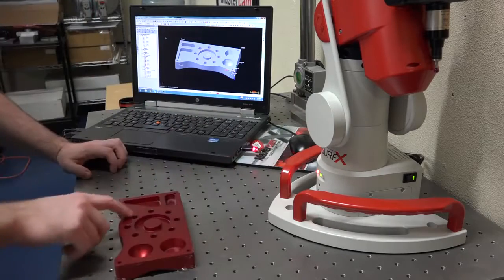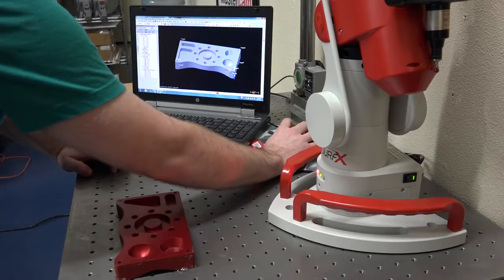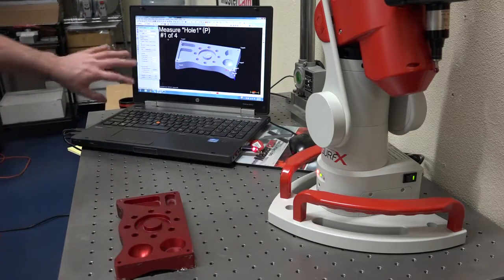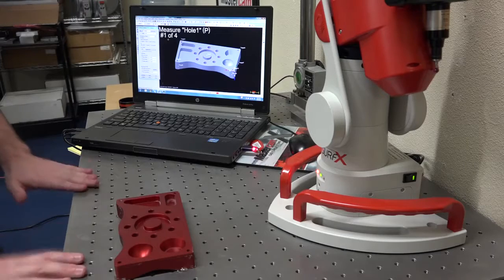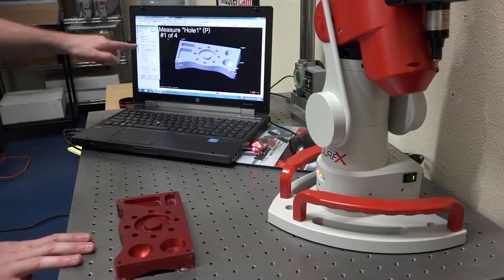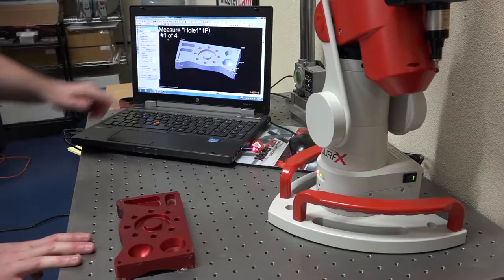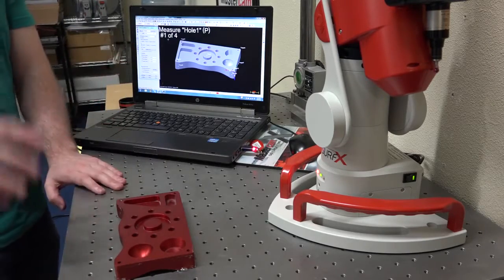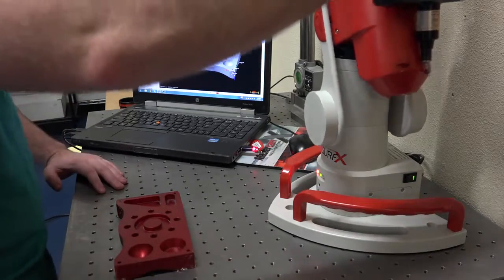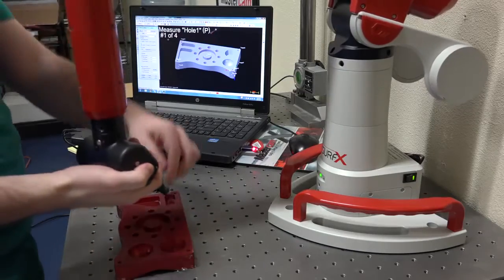Now I'm going to do these blind holes down here in this larger diameter. So I'm going to use my circle tool. In this I have options for probe compensation. Usually the automatic compensation works a lot of the time, but you also have the option to force it to use the inner diameter, no compensation, or the outer diameter. So it depends what side of the circle you're measuring. I'll leave it at auto, and this is determined by the direction the arm faces when it's measured. It's very decent at figuring out where it is in space.